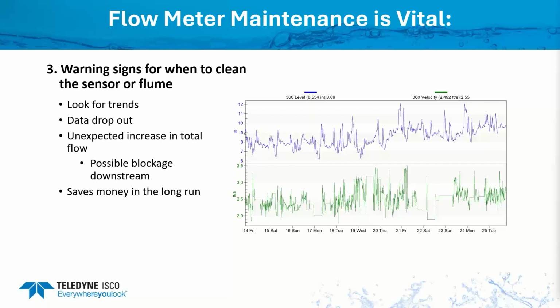So when I mentioned looking for dropouts, I'm looking for the trends. When you're looking at the green velocity down here on the bottom, over time you're going to see that you have good velocity readings going up and down. But then if you start getting flat spots, that's usually an indication that it's just holding on to the last known reading because it was having trouble getting a velocity reading. And usually the cause of that is sediment building up on the front of that sensor. A little bit of sediment covering the front, you're going to get a few dropouts, but the more sediment that covers the sensor, then you may find that it goes into complete failure.